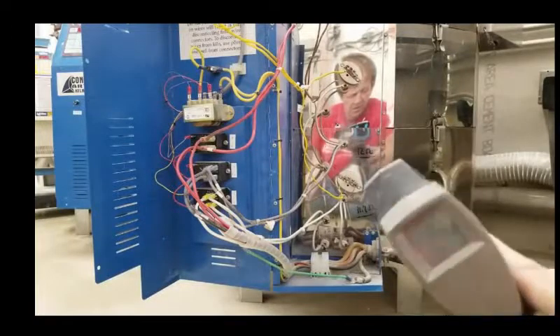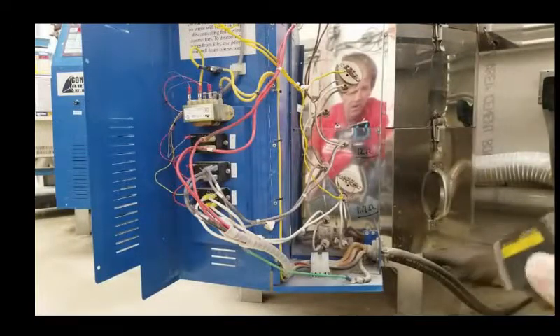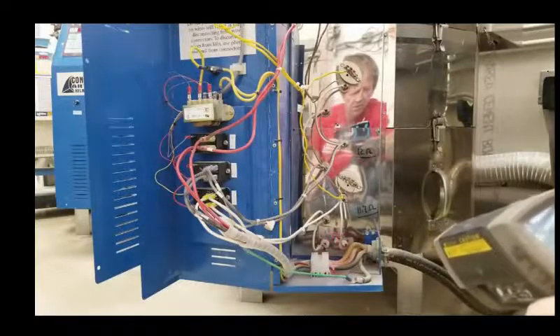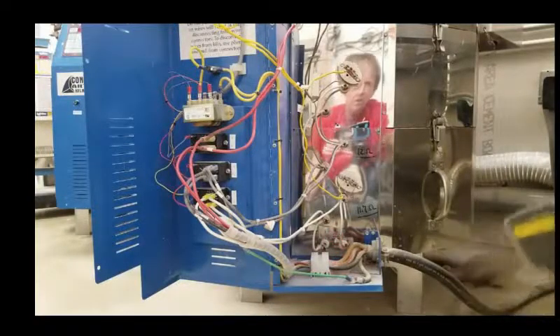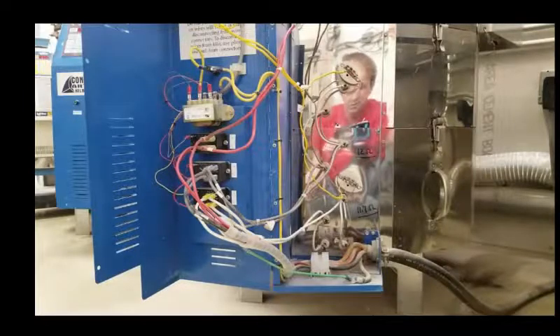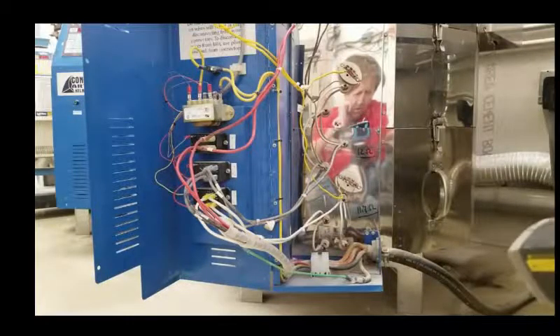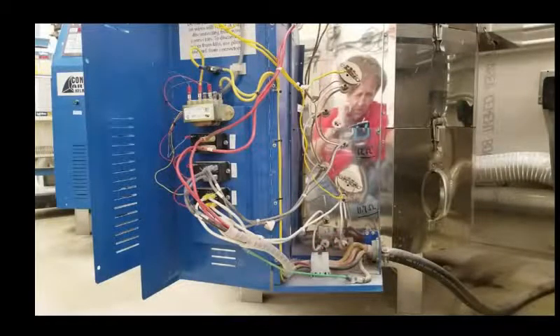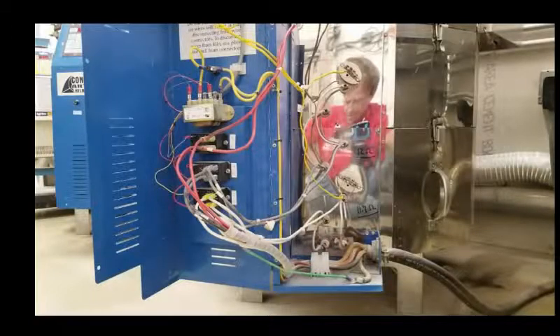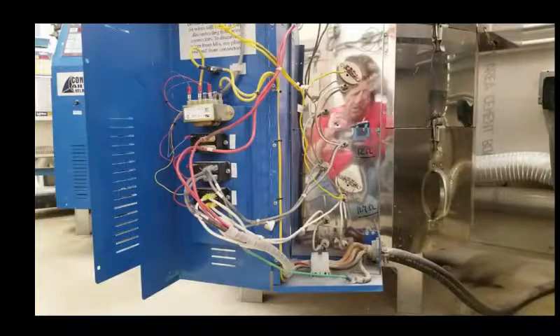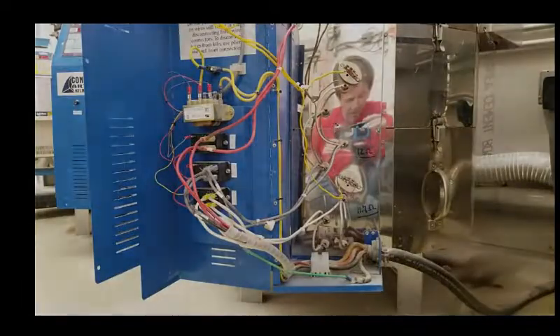This isn't the greatest device, but it's very economical. And I'll probably go through the rest of the machine just looking for really hot spots. And this is kind of a super way to go diagnose this machine. So we found one. This is a full checkup. So we did our visual. We checked all of our connections visually, and we tugged on them all. They're all tight. And now we're going to shut the machine off because we know this is hot down there, and we're going to pull that apart, take a look at it, and probably clean it up and put it all back together nice and tight. So stand by for that.